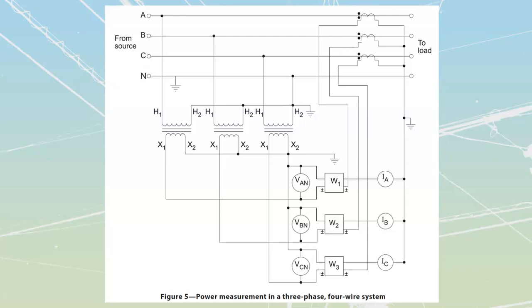There are 2 separate ways we can do that, depending on whether we are delta or whether we are Y. First, I want to go up top and count the number of active lines from the source. I see that I've got 4 active lines, and I can take the number of active lines minus 1, which tells me I need 3 wattmeter elements. A wattmeter element is a VT and a CT that are connected together - my wattmeter needs to have its potential, as well as the current that is associated with it.